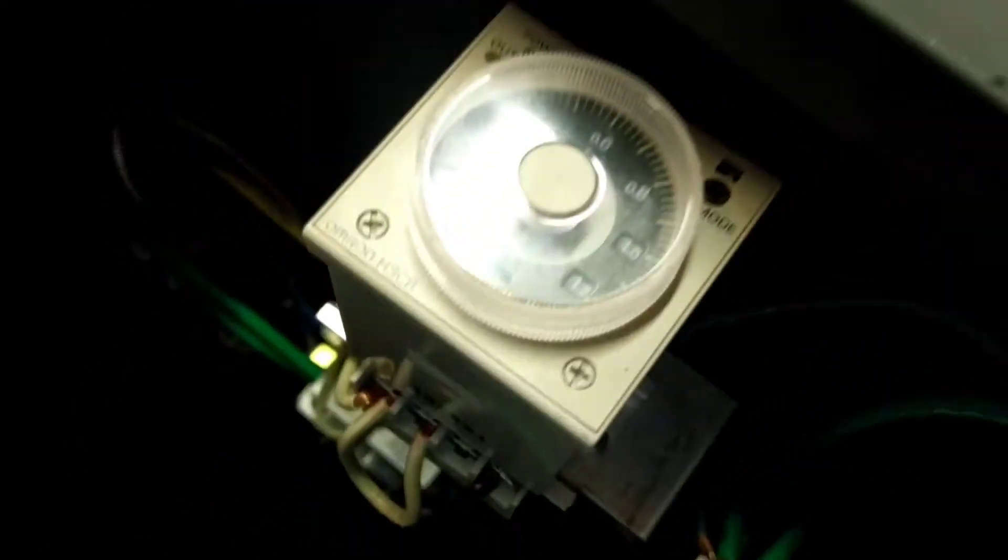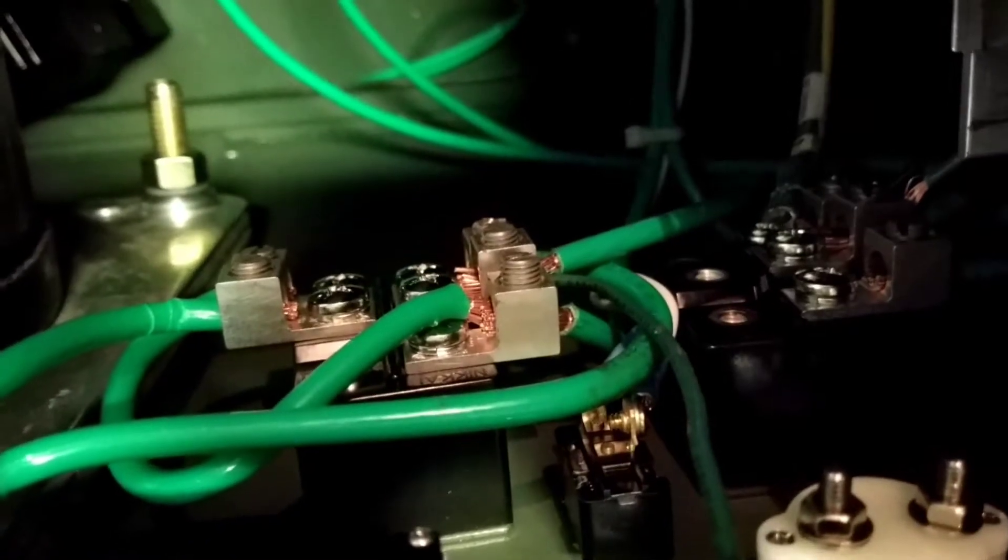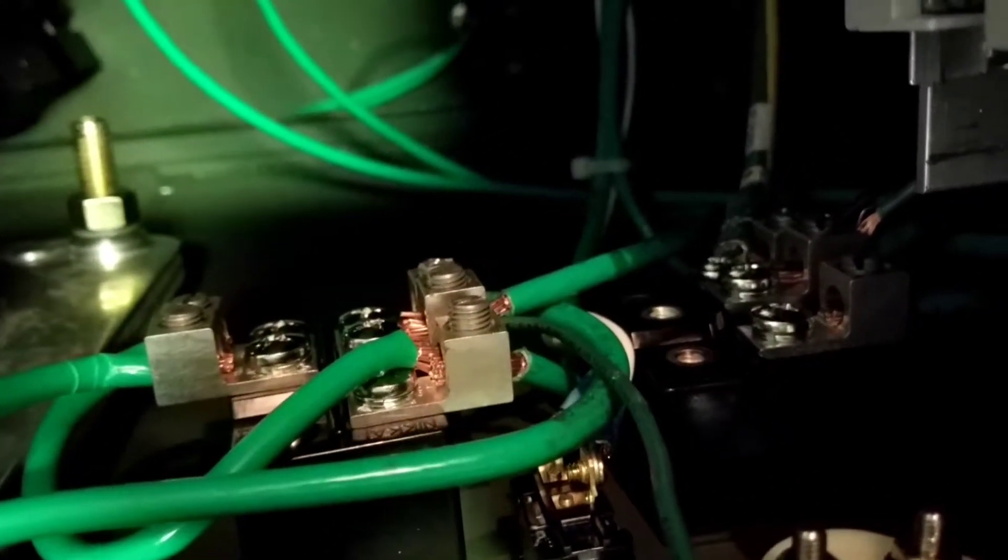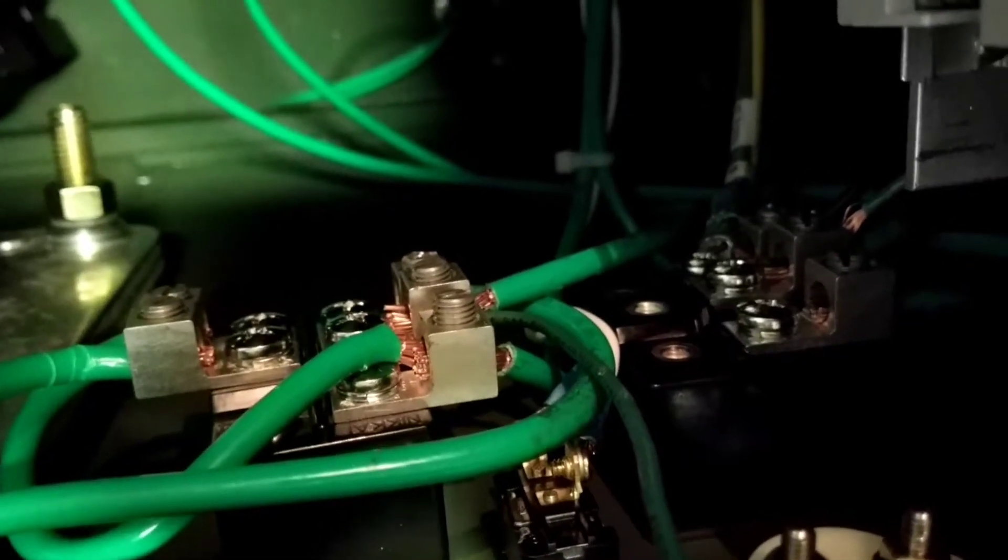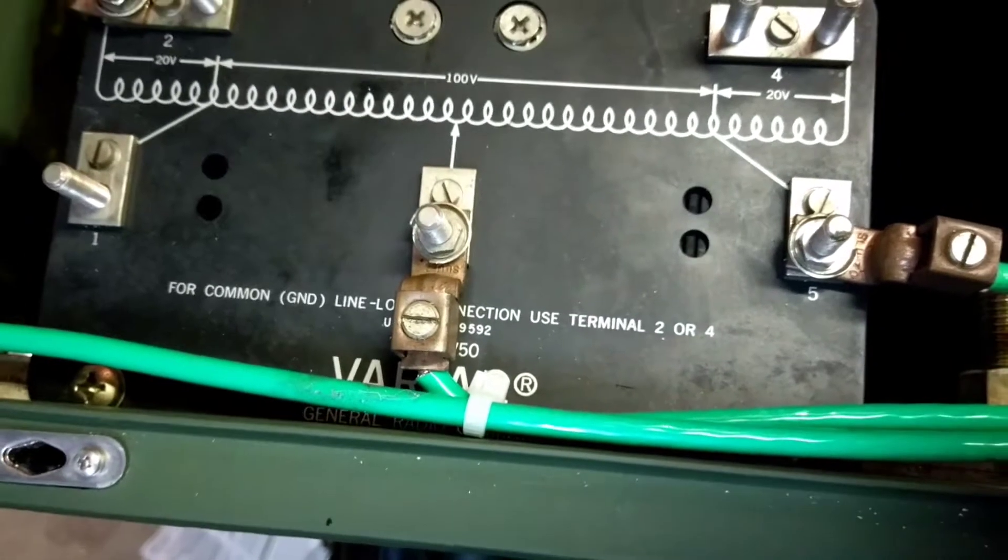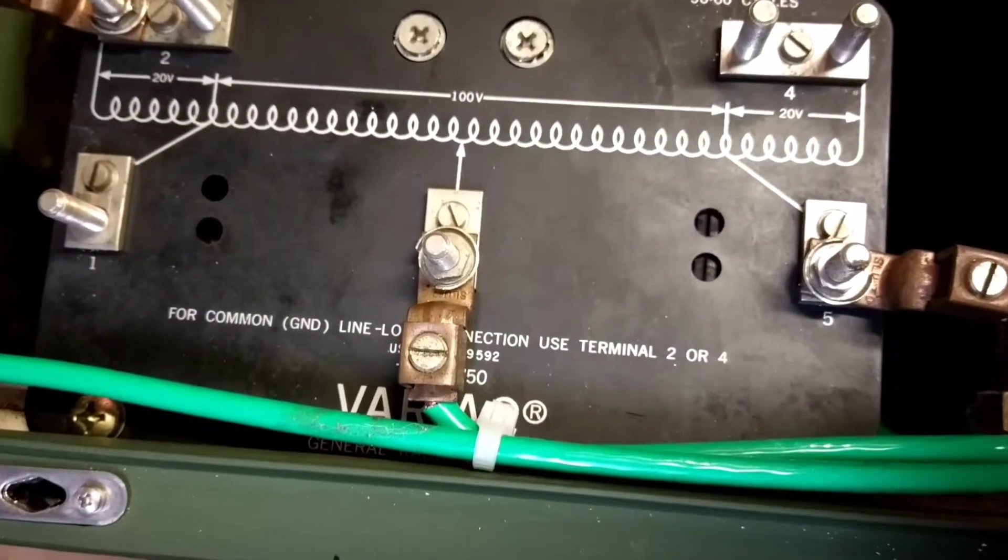Then a timer module, and then a pair of very substantial double pole switches rated at 50 amps each. And then the actual variac. The variac is only a 120 volt 50 amp unit, but I've got a way around that and it's through the use of these switches how it's arranged.